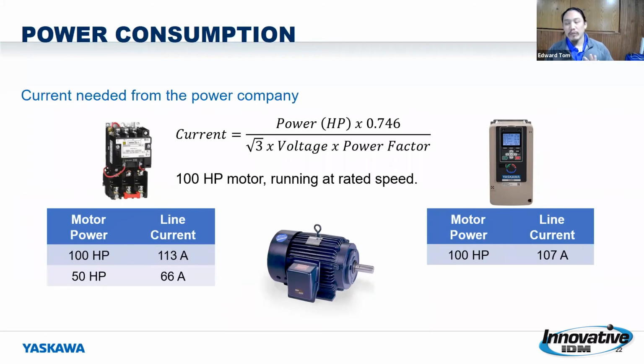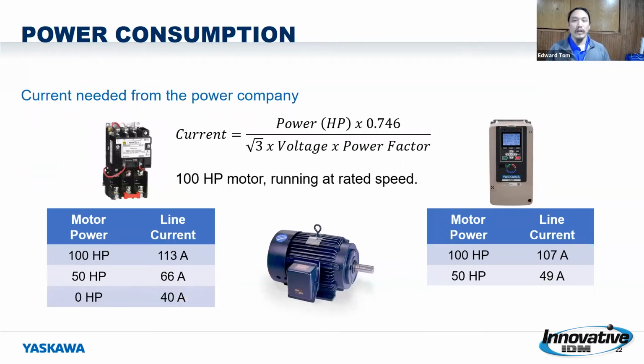Now I'm going to drop that to 50 horsepower, 66 amps. Now, if I follow the same pattern, you might go, it's going to be lower. Well, definitely. We're now less than half the line current required on there. So now the amount of current that's out there, the amount of losses in your system have also decreased. Now, what if I'm just running my motor across the line? I have no load out there. It's just running. I'm waiting for product to show up in there.